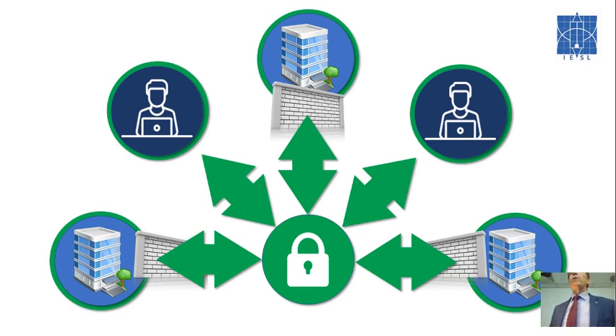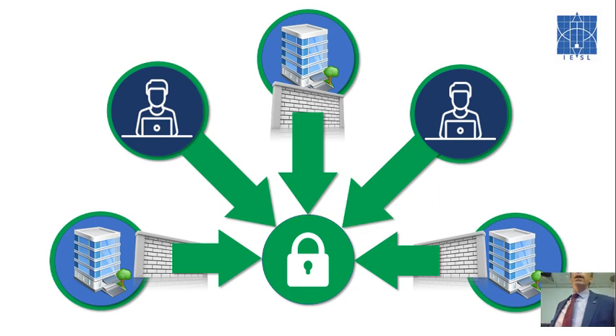That's part of the reason why ASHRAE got involved and said, okay, we need to put forward a solution within the standard so that we all understand how that information is passed around, and they came up with this. The important part is that it's a connection from inside the building through the firewall out, and typically IT people aren't upset about that, because you could probably walk into any of your buildings here, unless it's a high security building, go to your computer, open your web browser and search something, because you're coming from inside your building through the company's firewall to outside. That's not a security risk. It's when somebody's outside trying to come in through the open firewall that's the possible danger.